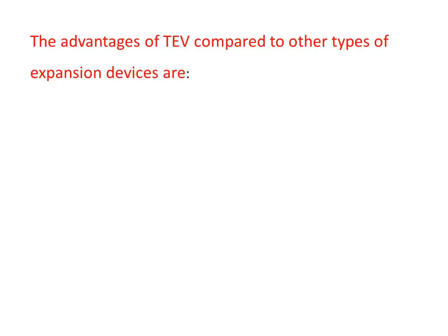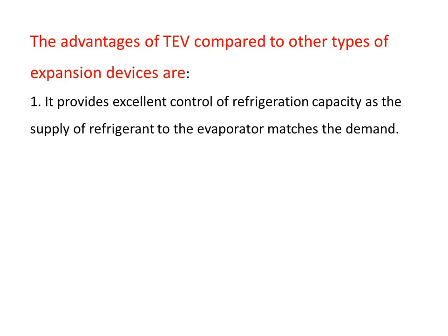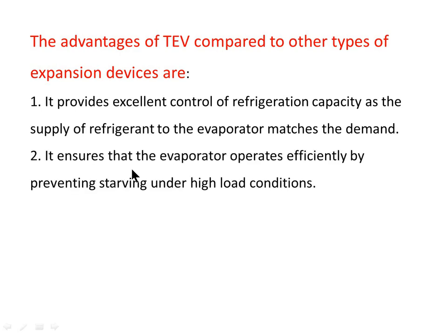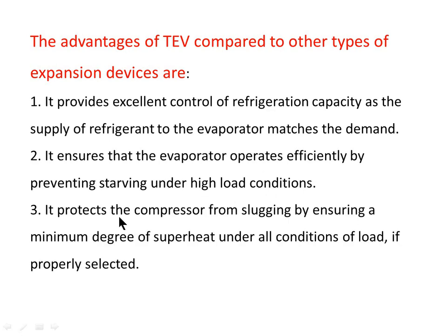The advantages of the thermostatic expansion valve compared to other expansion devices are: it provides excellent control of refrigeration capacity as the supply of refrigerant to the evaporator matches the demand; it ensures the evaporator operates efficiently by preventing starving under high load conditions; and it protects the compressor from slugging by ensuring a minimum degree of superheat under all conditions of load, if properly selected.